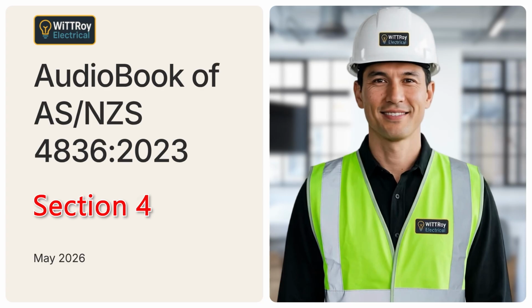Clause 4.3, Specific Situations. Clause 4.3 introduces the specific situations covered in this section. These include work on or near exposed energized conductors and live conductive parts, capacitors, hazardous areas, trafficable areas, areas of reduced mobility, lighting, batteries and DC supplies, high voltage producing equipment, induced voltage, asbestos, PCB materials, lightning, cutting cables, removing out-of-service equipment, and leaving work unfinished. Each situation has its own hazards. Each situation needs suitable controls.